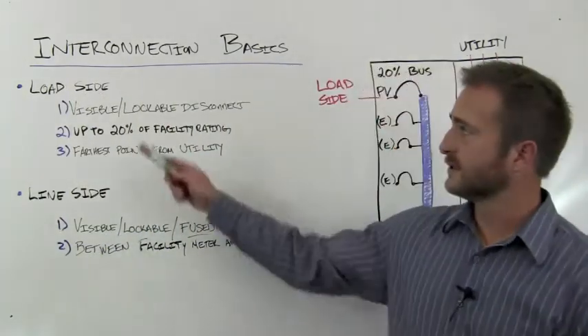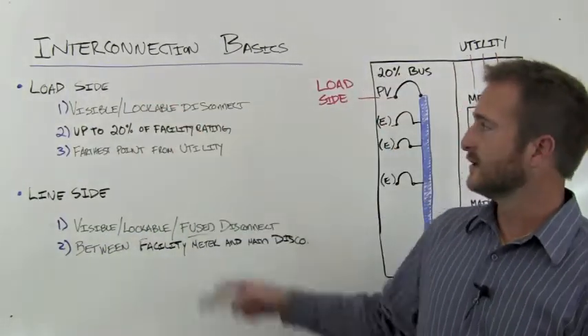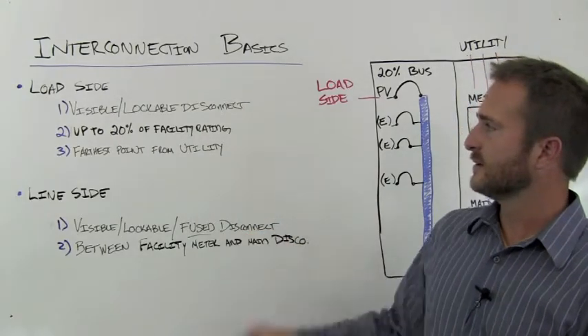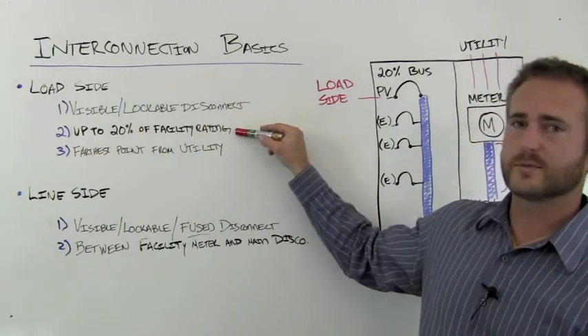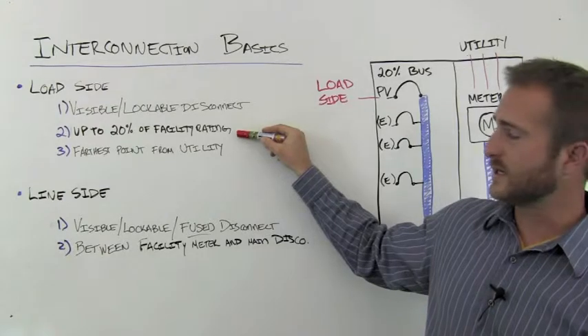So it's really pretty simple. To go back over those main points: load side, line side—you're going to need a visible lockable disconnect in either case. Load side, you can install up to 20% of the rating of your main gear.